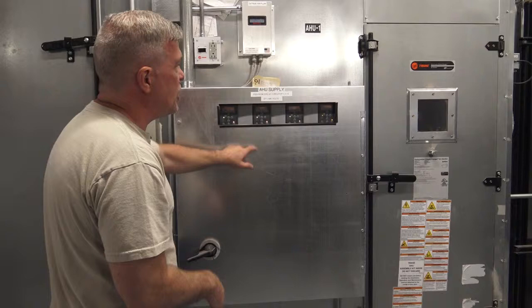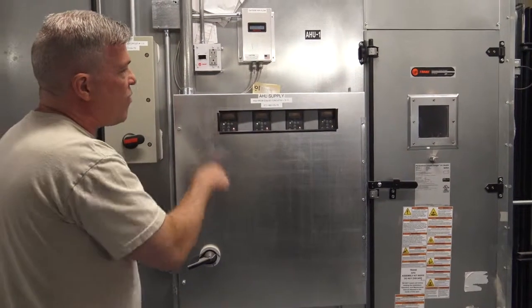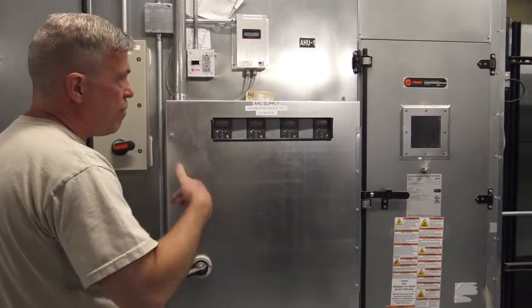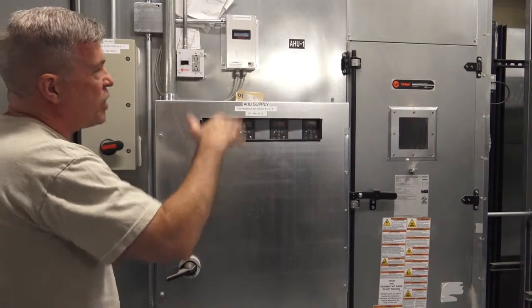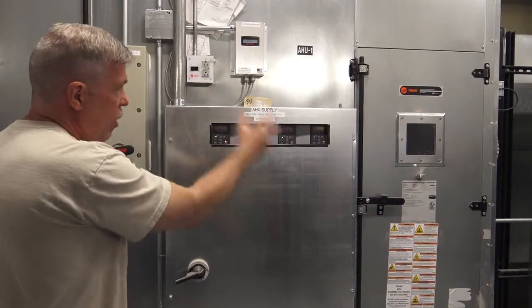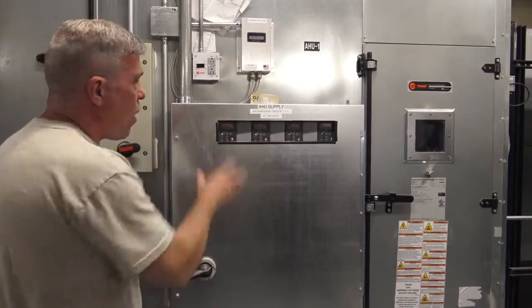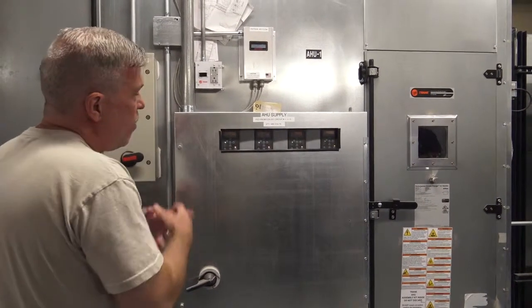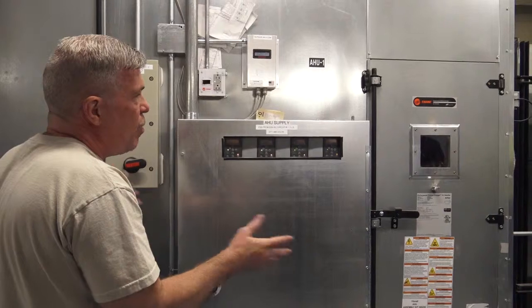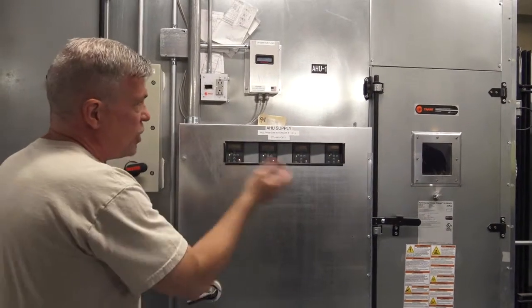Big thing to know, because there are 4 of them, is if one of them fails out, it'll actually start spinning backwards, which causes your differential to drop, and it'll just start circulating air here. So it's a good thing to correct the problem as soon as you can. The building will still probably run okay, but you might see a slowdown in the air supply.